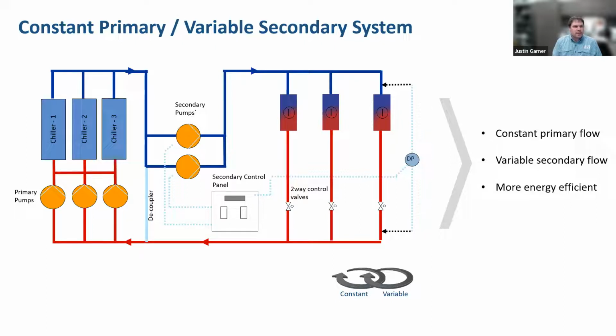Some of these systems still had a remote bypass out in the system, but you'd have to have a building automation or some other kind of controller that was controlling DP or flow in the system. Oftentimes it was DP measured two-thirds or at the furthest point in the system to control your secondary pumps. The challenge with this system became if your secondary pumps overpumped your primary, your temperatures would start rising in your loop. And so it creates a different control strategy there, but it was a way to start reducing some of the pump energy, at least in the furthest parts of the system. Go ahead and go to the next one, Pete.